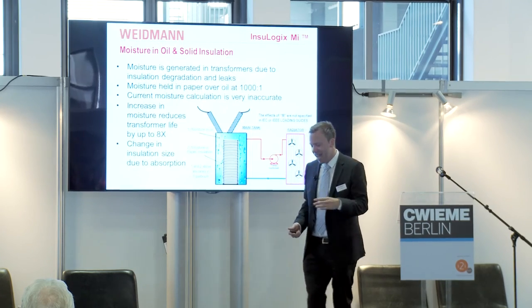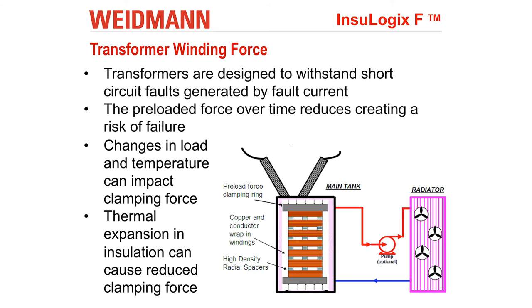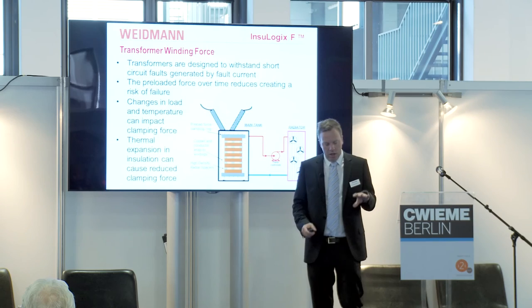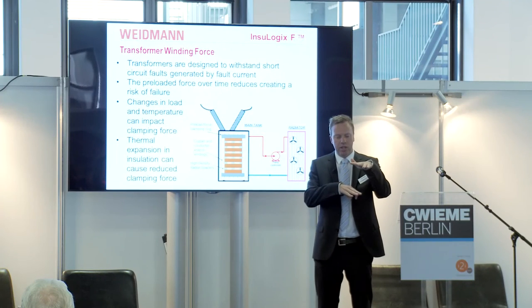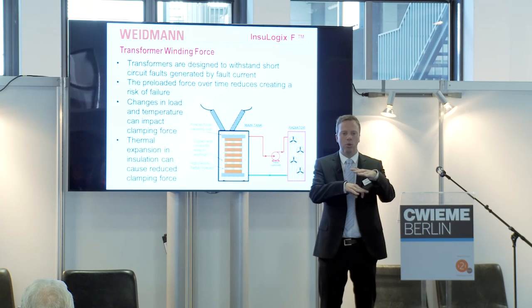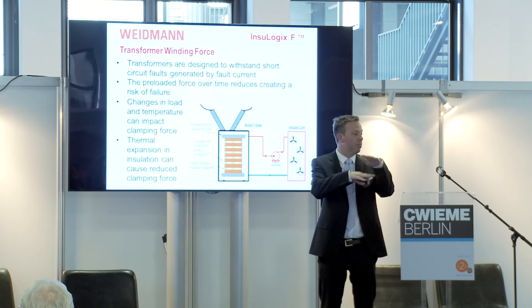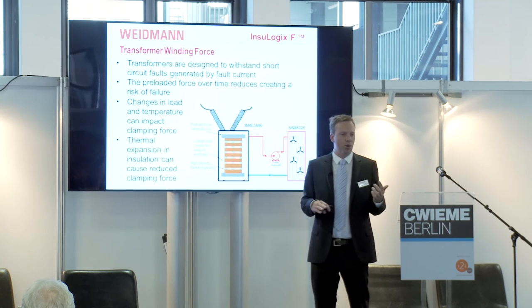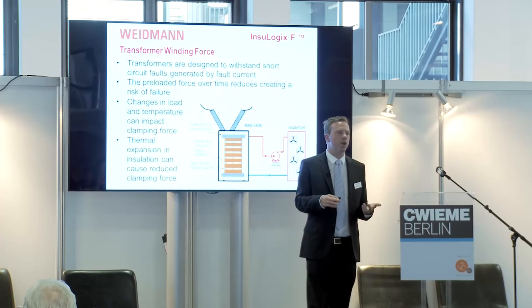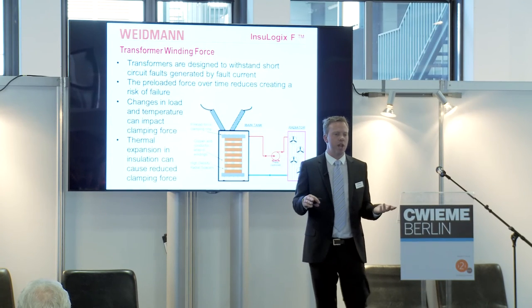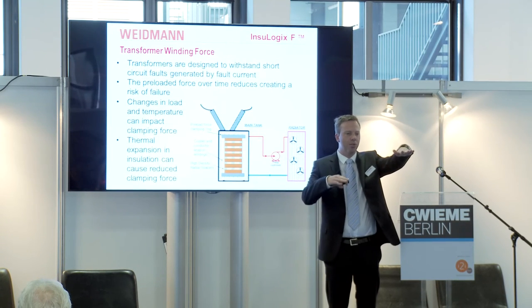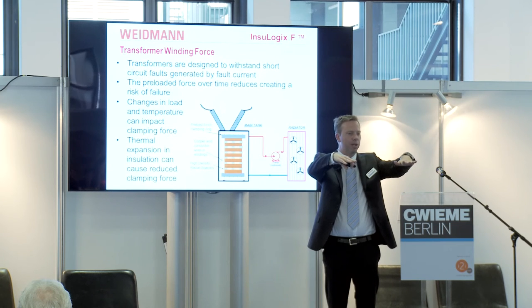So with that said, that links us to the winding force of the transformer. In the event of a short circuit, as I'm sure you're all aware as people in the power industry, the last thing you need is a transformer that's not clamped correctly. Because when a short circuit goes through the transformer, your windings can move and ultimately it can destroy the transformer. So I asked the question, well, why don't we just use a strain gauge at the top of the transformer, just measure the pressure of the clamping plate?